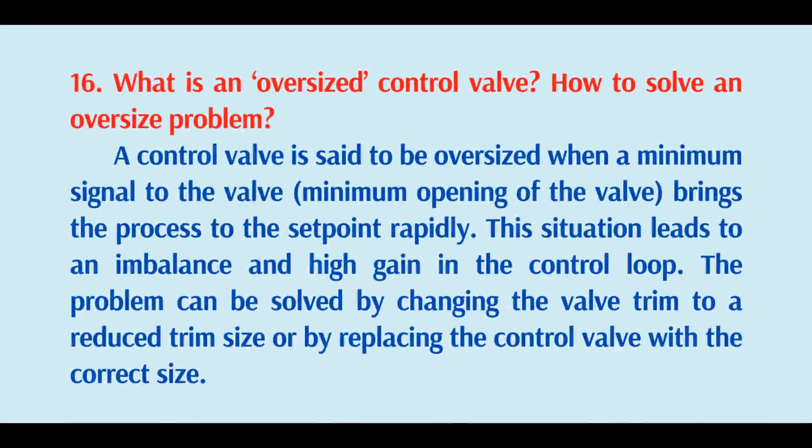What is an oversized control valve and how to solve an oversized problem? A control valve is said to be oversized when the minimum signal to the valve — minimum opening of the valve — brings the process to the set point rapidly. This leads to imbalance and high gain in the control loop. The problem can be solved by changing the valve trim to a reduced trim size or by replacing the control valve with the correct size.